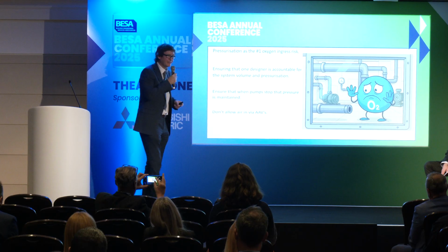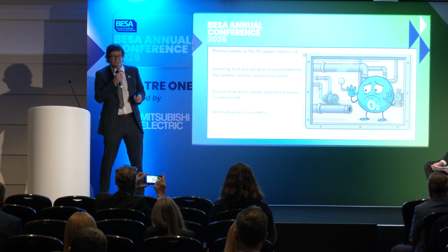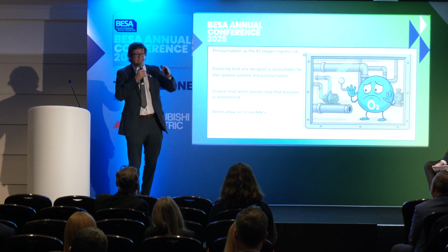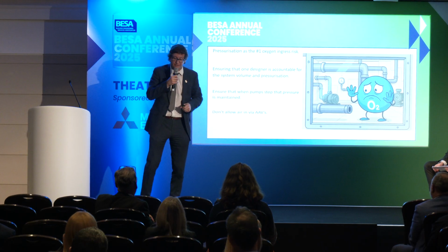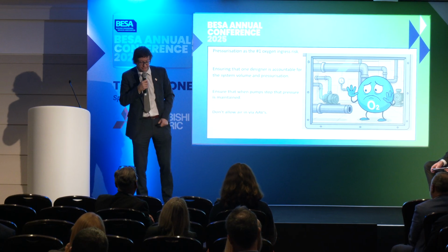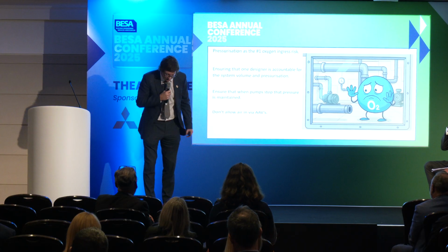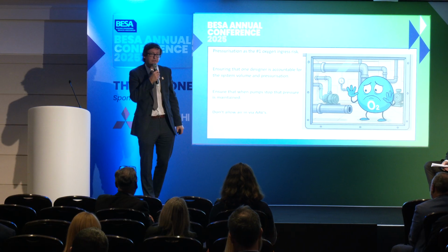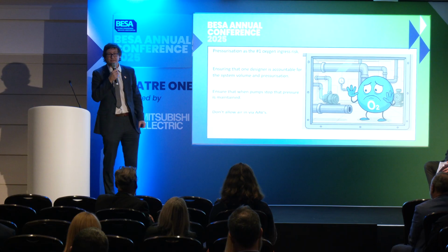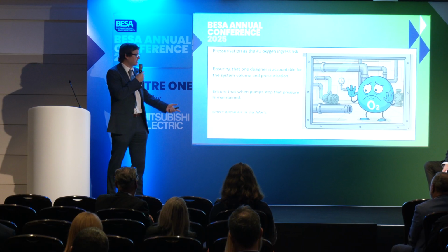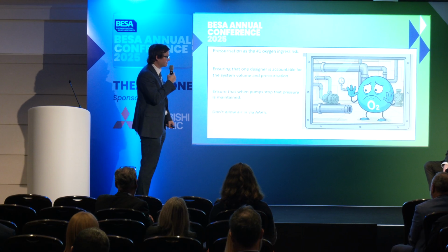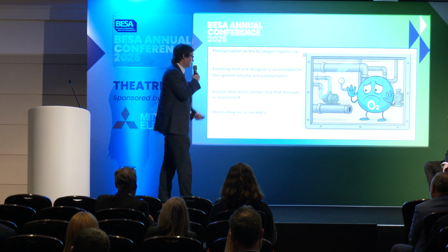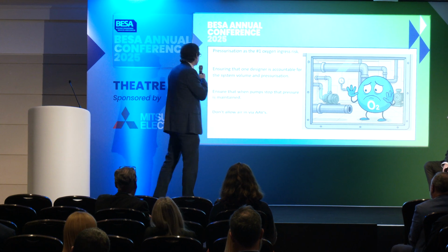I've done jobs near King's Cross where I've gone to the roof of a client's site with all the radiators and a plastic system corroding. I unscrewed the air valve, and water was falling out the AHU, cooled down the riser. Pressurisation was completely wrong, all that air was just going in, and the only steel in the system was the radiators and the pressurisation buffer tanks, and they'd been eaten to shreds.